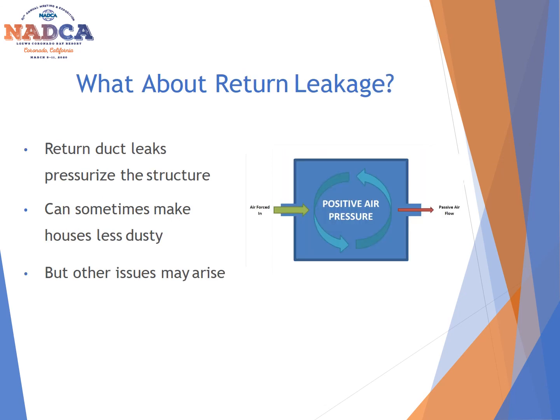We just talked about what would happen on the supply side of things and how you create a negative pressure inside of a building whenever you have leakage on the supply. But what happens when you have leakage on the return side of things? You're going to have a tendency to pressurize the entire facility. You may actually have less dust and fewer allergens being sucked in, depending on where that makeup air is coming from. But a lot of other issues can arise from these circumstances as well.